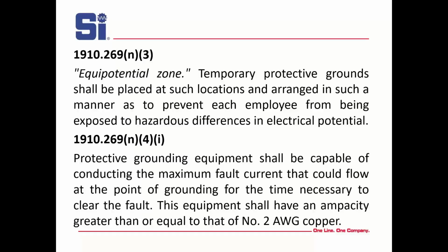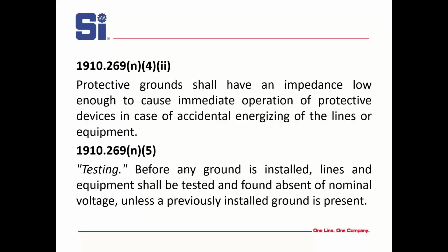The next section, N4, says protective grounding equipment shall be capable of conducting the maximum fault current that could flow at the point of grounding for the time necessary to clear the fault, and it can't be less than number 2 AWG copper. And we'll look at this a little more later. Grounds have to have a low impedance. They're designed with a low impedance. If they're connected correctly, they will have.